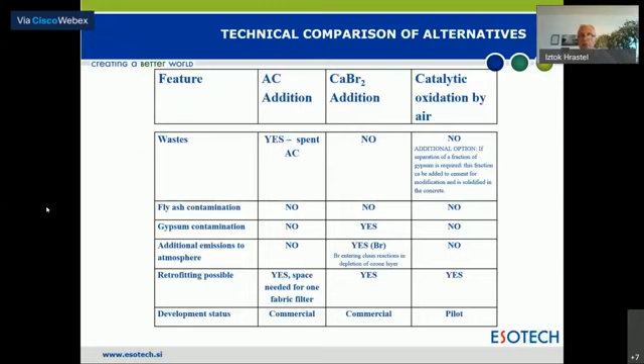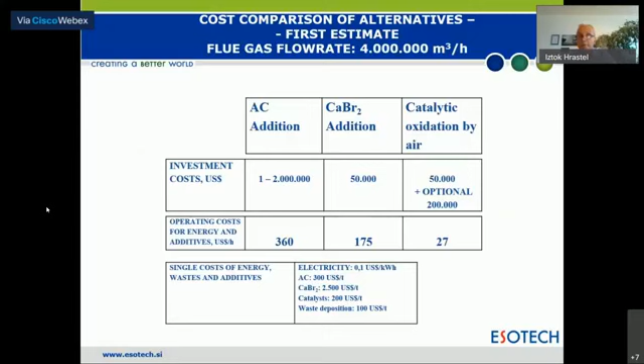Activated carbon addition requires very significant investment in equipment, such as a bag filter and additional fan, in order to separate mercury-contaminated carbon from the fly ash, which is otherwise used by construction companies. Operating costs are high due to electricity consumption, activated carbon consumption, and hazardous waste generation.